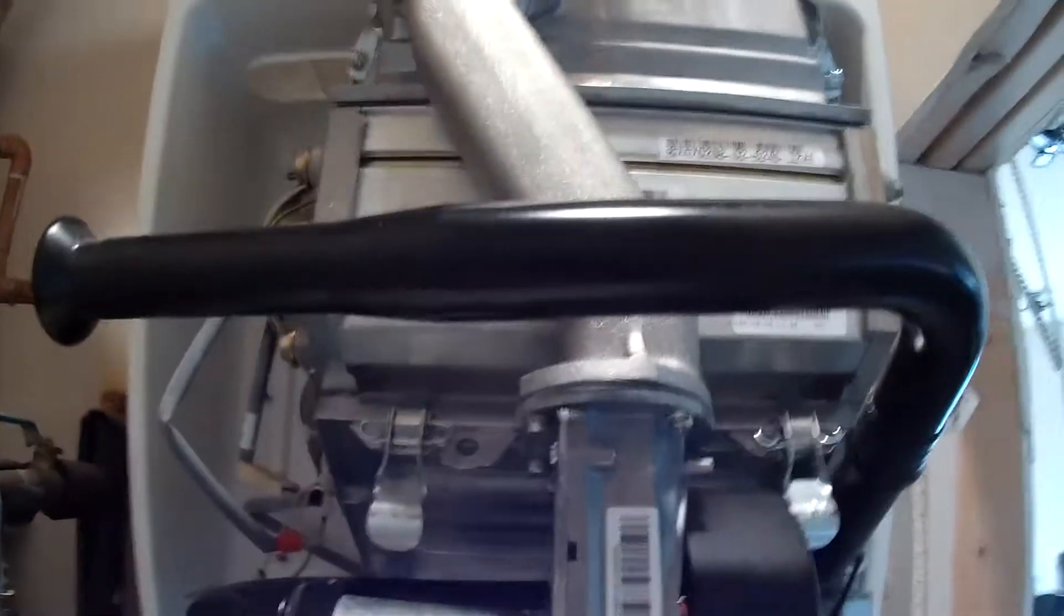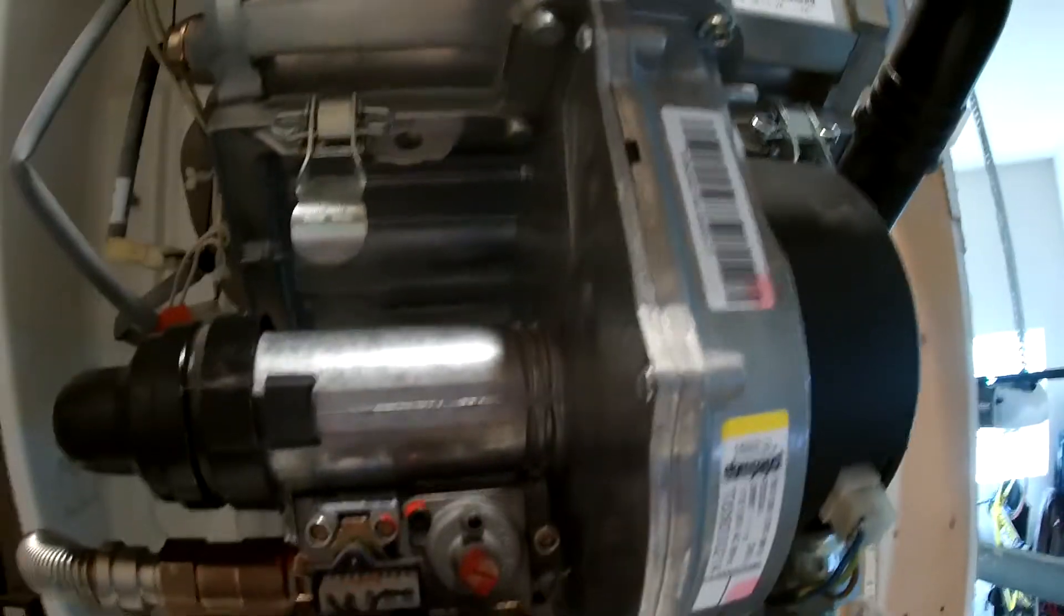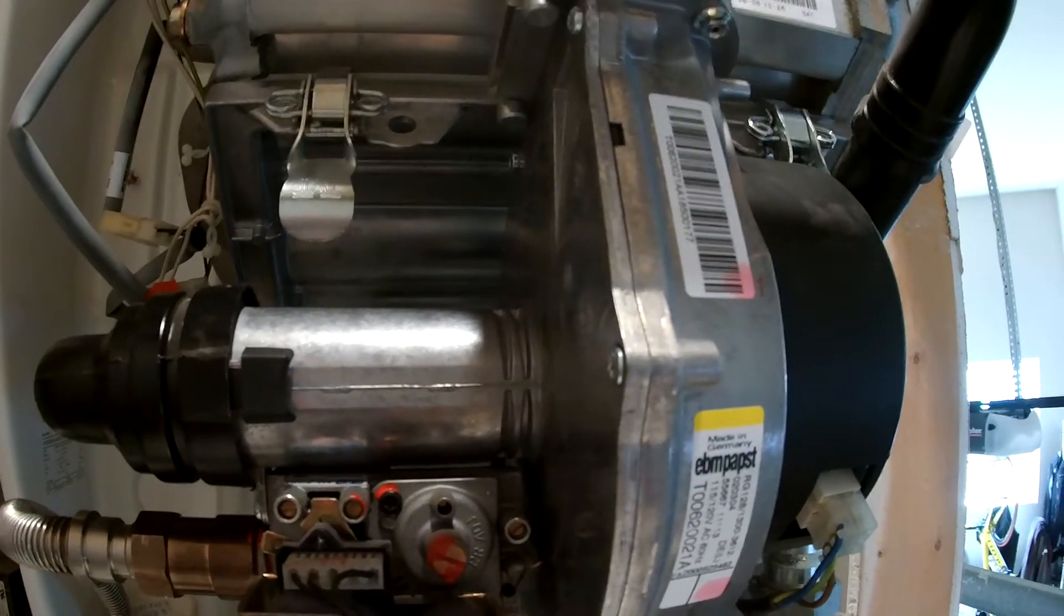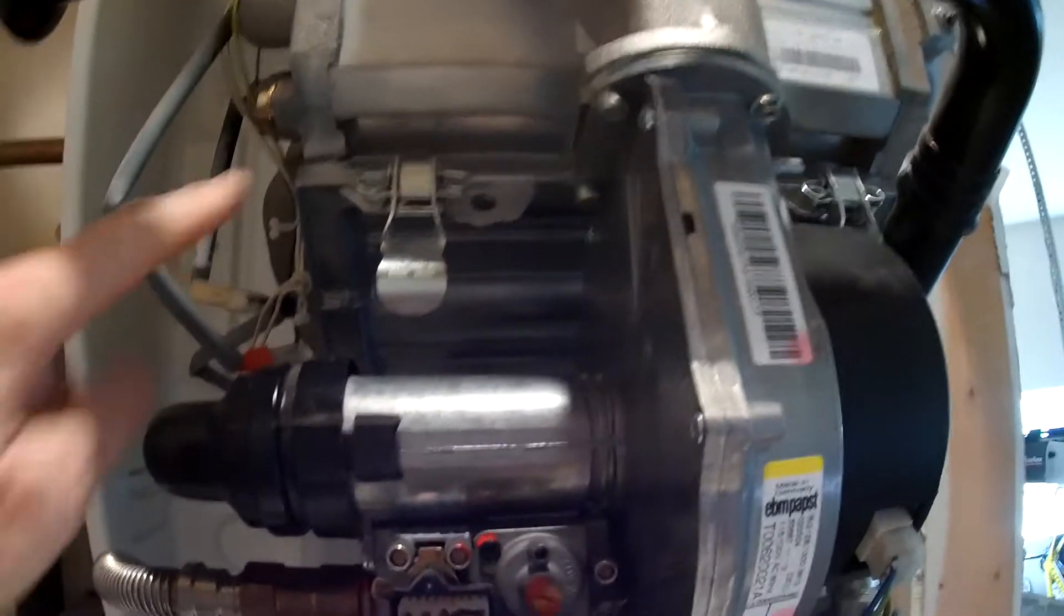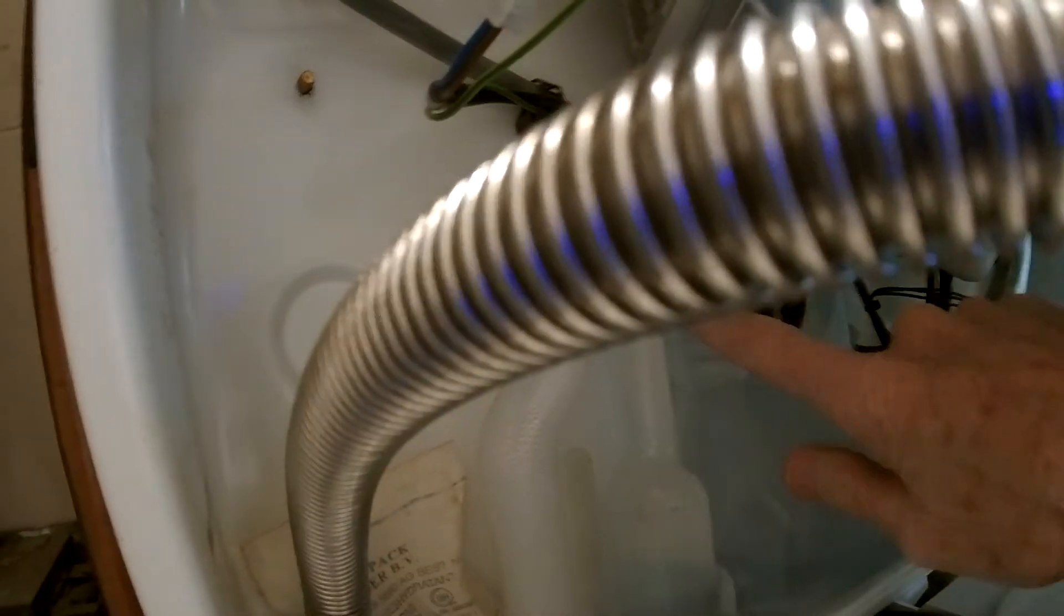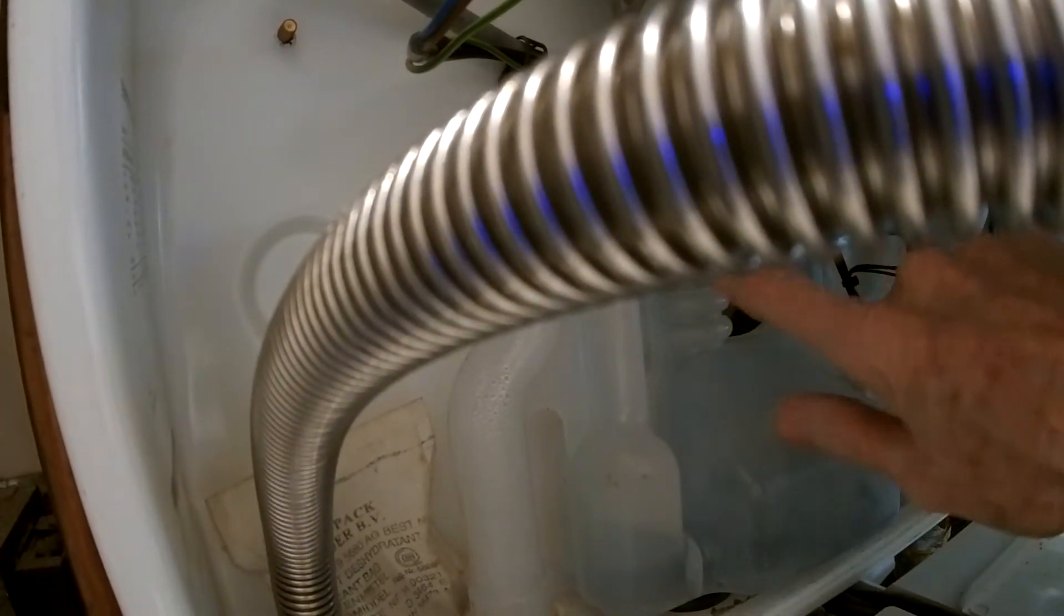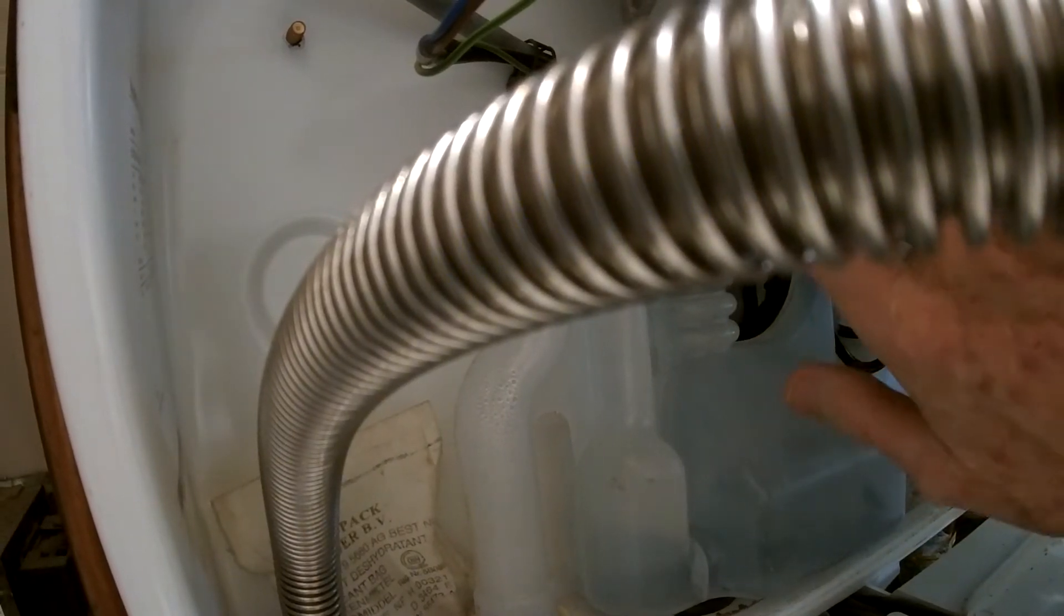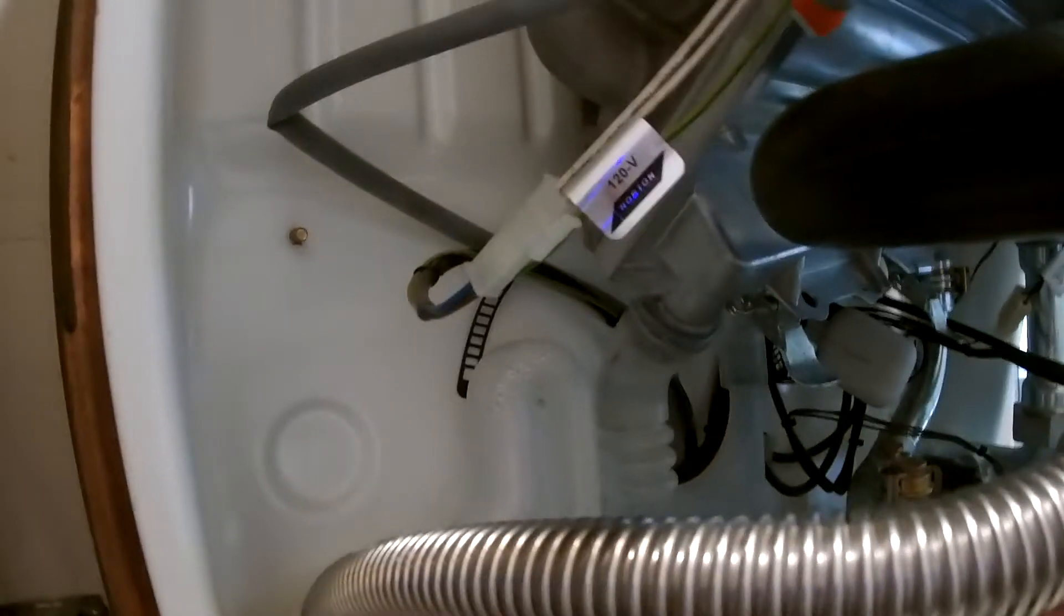Now while I was doing it, I decided since I had this off and I could see the coils inside, really a lot of buildup of deposits. So I decided to take the bottom plate off, give me full access to all the coils. It's been about three hours cleaning though. Very difficult to clean. Very difficult to get all the stuff off. This bottom plate is a condensate catching plate and it's very dirty with buildup too. Be very careful when you pull this off because it is hooked up to this siphon overflow condensate drip bottle. And this right here will break if you're not careful with it. But slide this out. This will then come off. This comes out. Clean it. Fill it up with water before you put it back on to keep the siphon working. So be very careful with that.